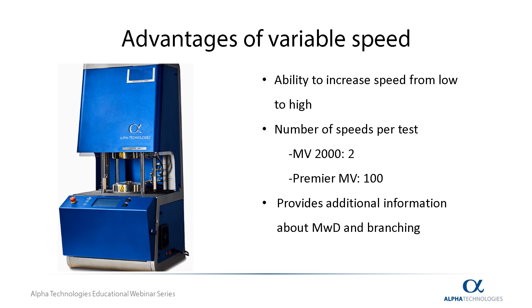However, instead of being limited to 2 RPM, the multi-speed Mooney is capable of rotating from 0.01 RPM to 20 RPM. This wider range of rotational speeds allows for valuable additional information to be collected. The Alpha Technologies Premier Series Mooney viscometer pictured here is capable of collecting data at 100 separate speeds during the same test.